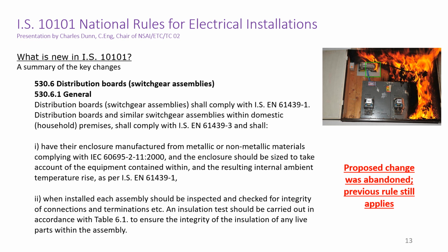A review of the existing rule, however, showed that boards are already required to comply with European standard EN 61439, which is a suite of rules that ensure that boards are non-combustible. EN 61439 requires boards to be type tested so that the components, the connections and the enclosure are not just resistant to fire. There's no point in having a board resistant to fire while all the rest of the building's on fire, but also that the board and its components do not actually cause the fire in the first place.